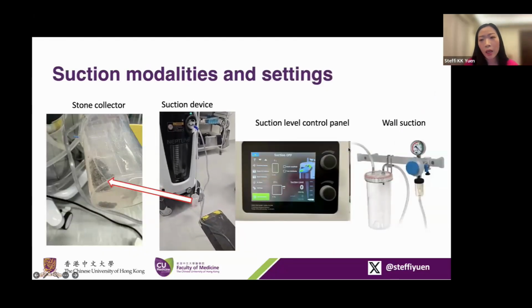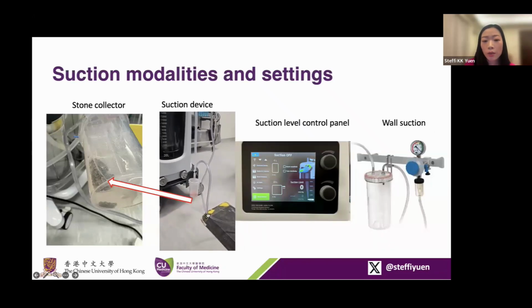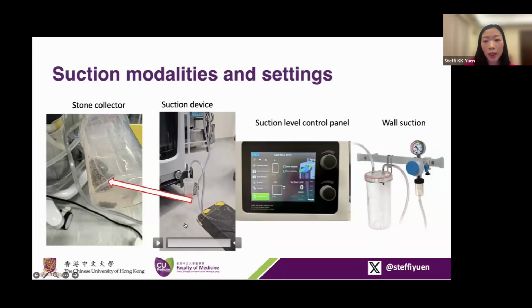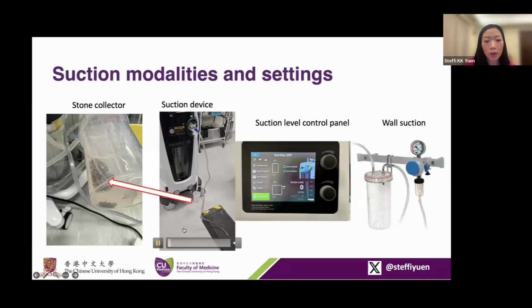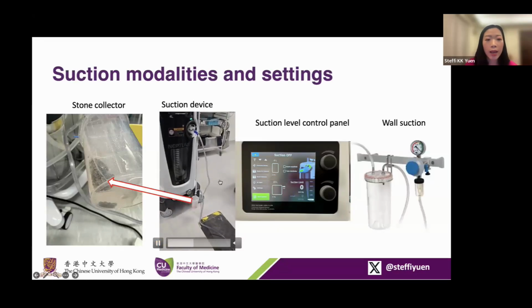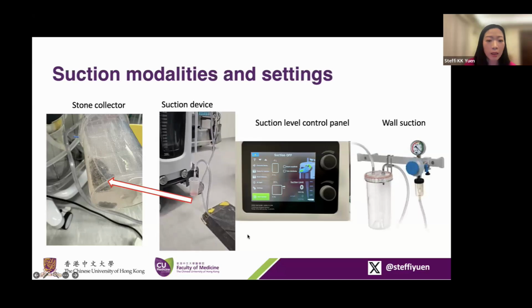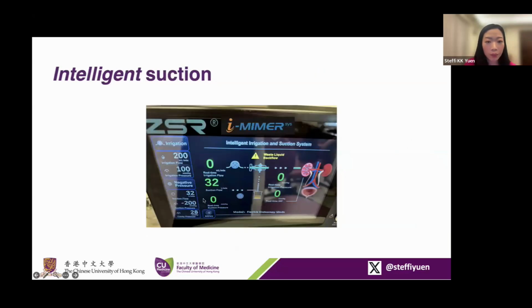For suction modality, I think a lot of us may be using wall suction, but the wall suction may not be very stable. If you set it at a certain pressure, it may not actually be suctioning at that pressure. And it may vary if a lot of people are using the centralized pressure at the same time. There are other devices such as the Neptune, which gives suction at graduated pressure, and you can more or less have a more steady negative pressure coming out. It also has intelligent suction. If the nurses connect the tubings incorrectly and there's backflow of fluid into the system, it will give you an alarm and stop as well.